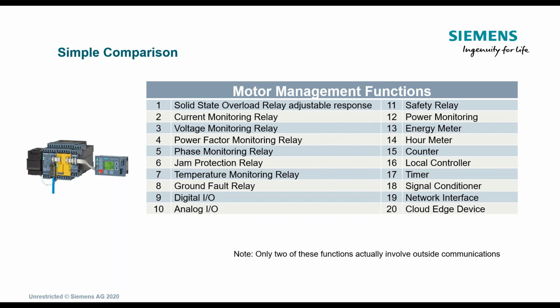Well, what about a motor management? What's a comparison to that? If we have a motor management system, what can we provide? Well, with SIMOCODE we can do a tremendous amount. It is a solid state overload. It is your current monitoring relay. It can be a voltage monitoring relay. It can be your power factor relay, a phase monitoring, loss of phase or phase imbalance. It could be your jam protection.